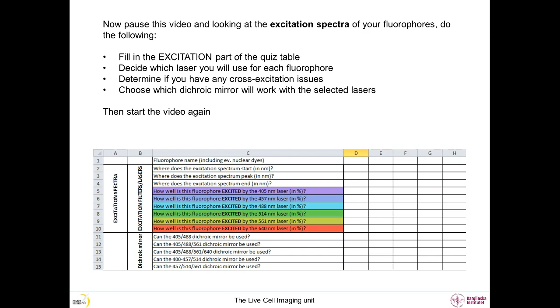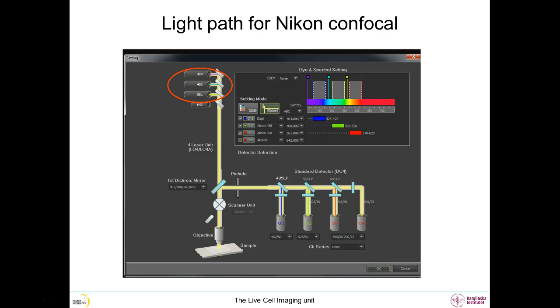Back to our example. The three lasers we have chosen are now on simultaneously, so the three fluorophores start emitting light at the same time. The dichroic mirror sends this complex emission light towards the detectors. The emission light then reaches secondary dichroic mirrors. These are long-pass filters that work exactly as the dichroic mirrors found in filter cubes. The emission light is split in two parts in front of the detector. The blue light below 495 nanometers is sent towards the first detector, whilst the rest continues towards the other detectors. The green light below 560 nanometers is then sent to the second detector, and so on. Additionally, each of these emission lights goes through emission filters, similarly to what happens in filter cubes. And here, you can see a summary of the whole light path, showing lasers and filters.